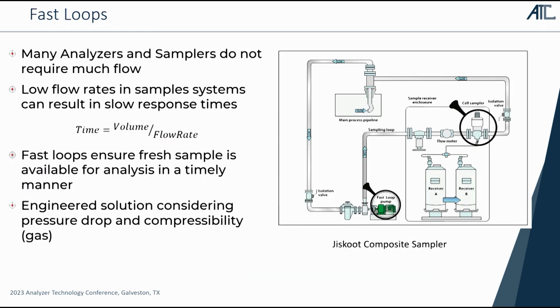Many analyzers and samplers don't require a lot of flow to operate, but we need flow in the fast loop to get a good response time. If you've been through the Tony Waters training or came to my class this week, you know we talk about how the time delay in a system is the volume divided by the flow rate. So if we want fast response, we either have to keep our sample system volumes low, or we have to have a lot of flow.